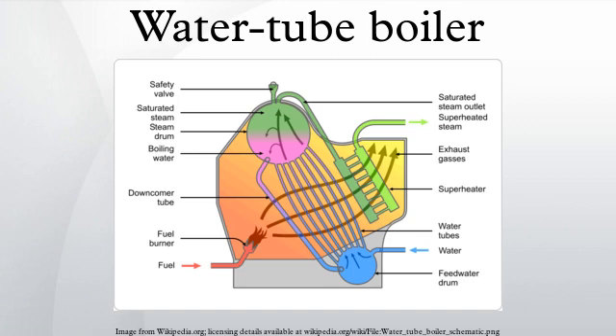It consists of a large steam drum vertically connected to a smaller water drum via multiple steam generating tubes. These are surrounded by walls made up of larger water-filled tubes, which make up the furnace.